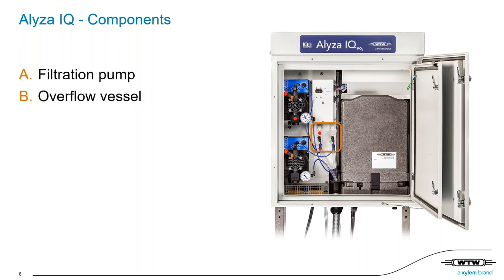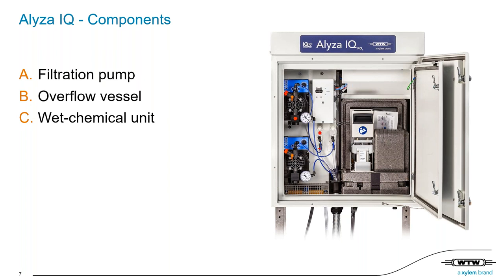Here you see the two overflow vessels. They are designed by us and made clear so that you can visually inspect it for bubbles or any solids buildup, and it can be easily removed and cleaned. This is the wet chemical unit. It is insulated and has a constant inner temperature of 20 degrees Celsius for optimized performance and reagent lifetime. Now let's see what's inside.